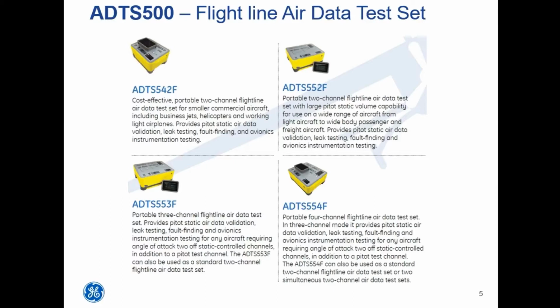And if we move across now to the 552, the platform size and footprint is the same now for the other units as well. It's a 2-channel unit. It comes as standard with a 15-month interval between calibrations and an optional 18-month, and we've been able to achieve that with our new sensor technology, which we've been developing for many years. It's another version of our resonant technology called TERPS, which is Trench Etched Resonant Pressure Sensor. I'll mention a little bit more about that in a moment.